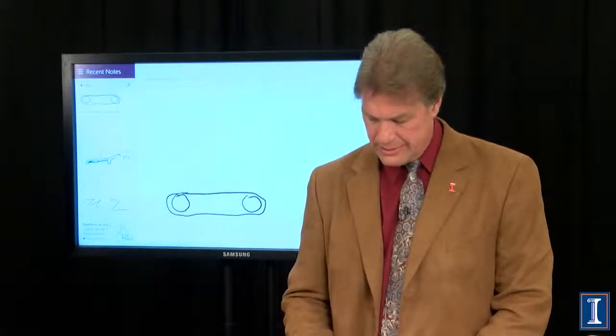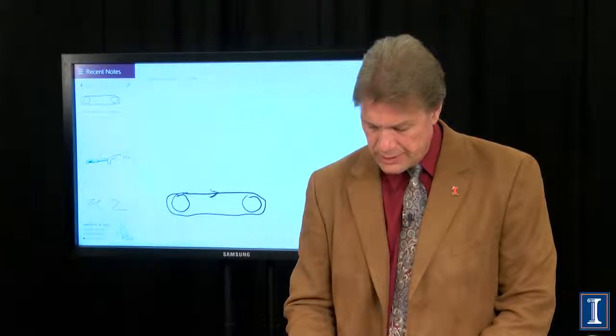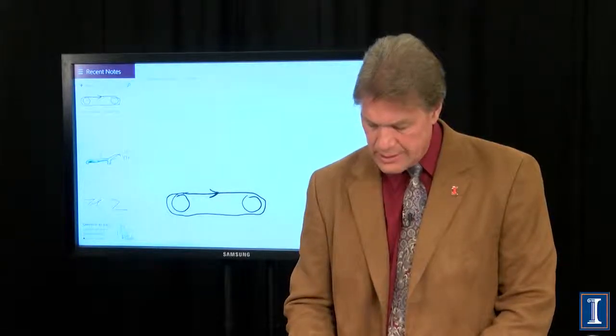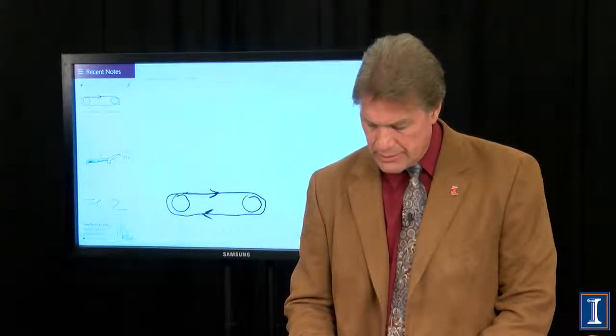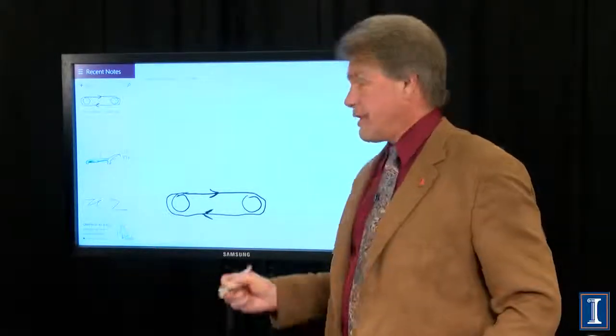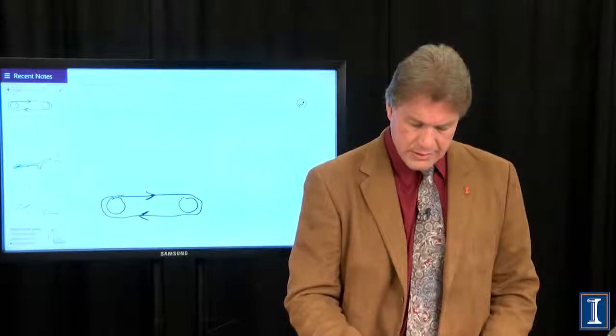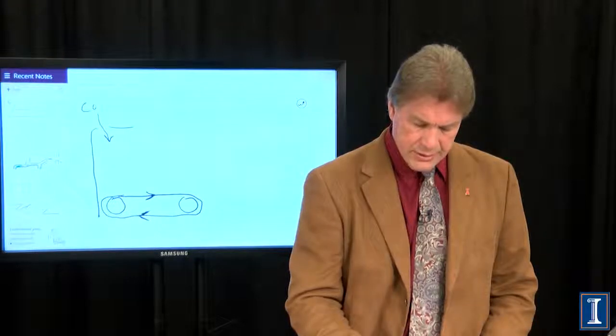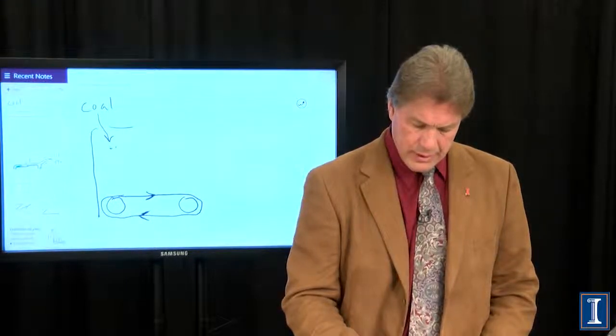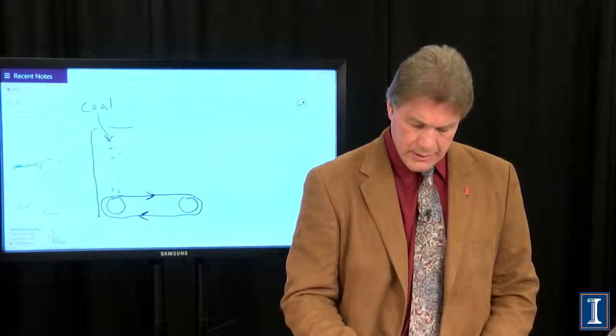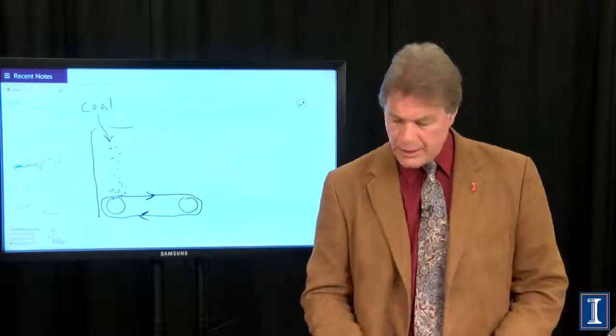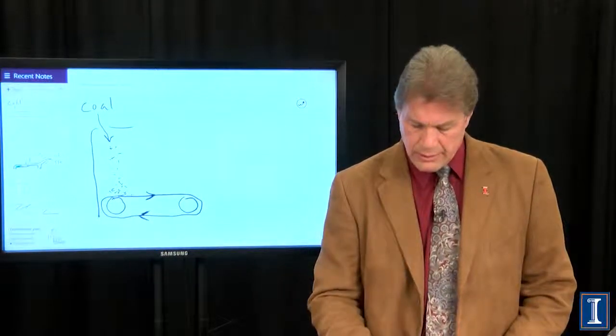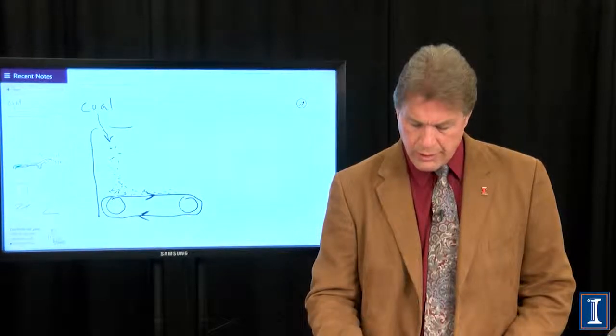What do I mean by a moving grate? Imagine the treads of a tank. This is a mesh, sort of like a chain link fence, that's moving around, going here in this diagram to the right. Somewhere up here, we have a coal hopper. We've got chunks of coal falling into this system. And because the grate is moving, the coal moves along with it.